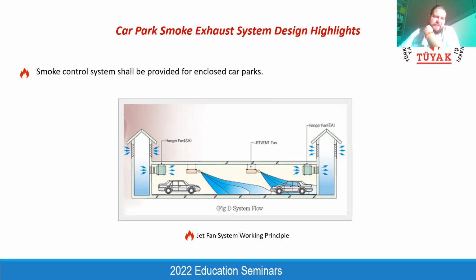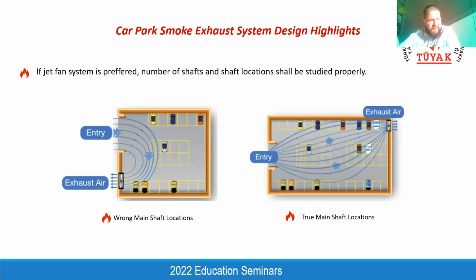The advantage of the jet fan system is that you don't have any hard duct. That means you are more flexible for the clear height of each floor. But for this system, you need to have large fresh air and also exhaust shafts for taking fresh air from outside of the building, and also to extract the smoke from the car park. Also for this system, the architect is responsible for the determination of the makeup air and exhaust air shafts. If you locate these shafts very close to each other, then you will face some bypass and you cannot extract the smoke from the enclosed car park area. That's why you need to coordinate.